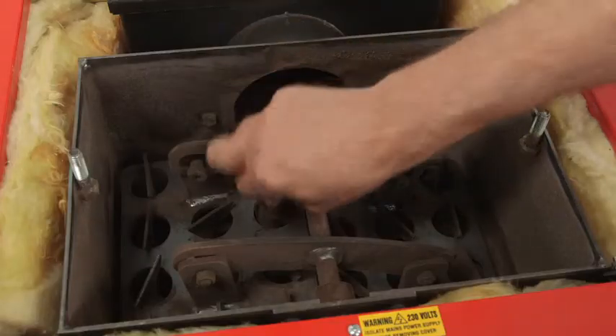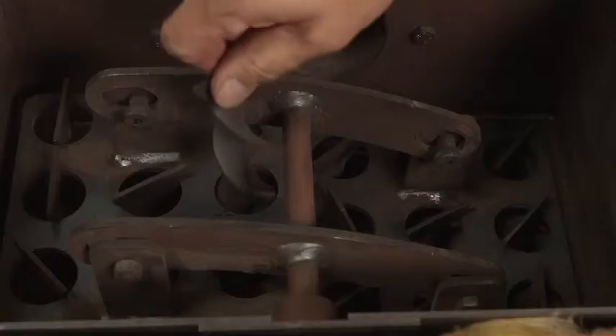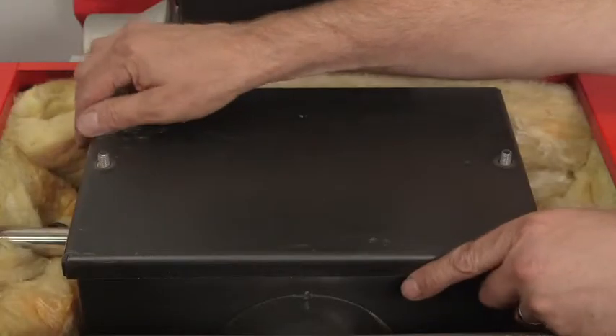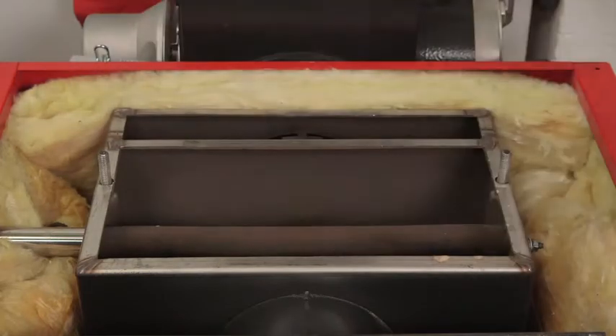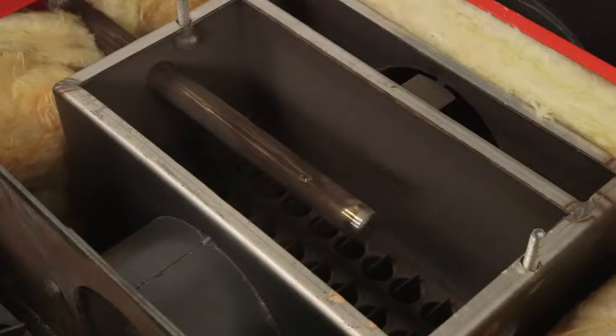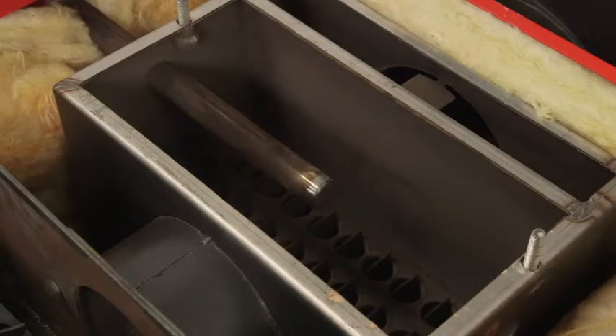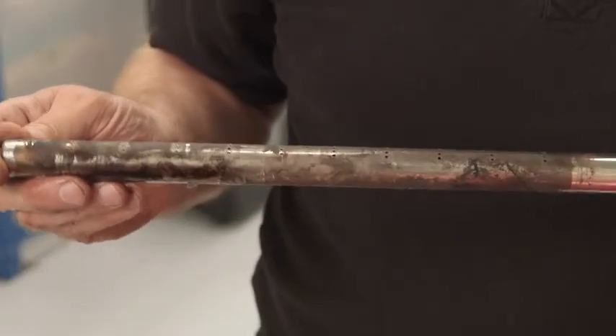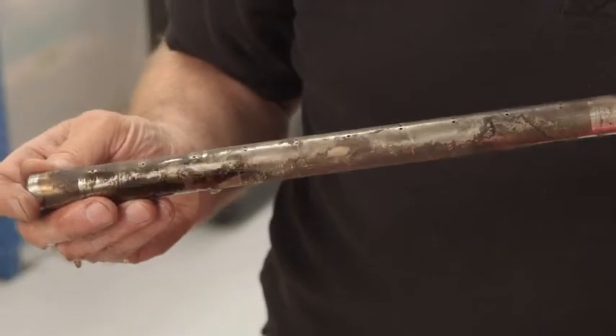Once you put the spirals back in, pick them up again and drop them a few centimetres to make sure they can move easily. Before you can get at the secondary heat exchanger, you'll need to shut off the cold water supply and remove the washdown manifold. Have a good look over it and make sure that the water holes are clear.